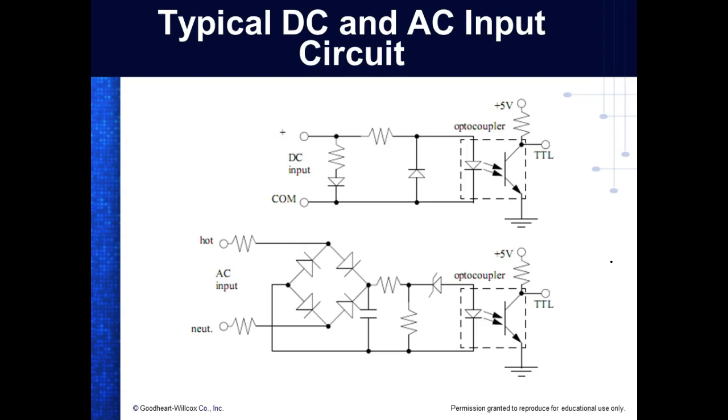And this is a photo transistor, which is what this guy does. So what I've got up here is this little remote for my TV, and I can flash lights, and that photo transistor picks that up. Right? You understand? I can drop this thing, and that doesn't hurt that one up there at all, because it's what? It's isolated. Where I'm bringing this input from the outside world, where we've got all these idiots out there, and I'm going to bring that into my PLC, and I'm not going to protect that? How many PLCs do you think we would blow up because guys hook up things backwards and stuff like that? So we isolate that.